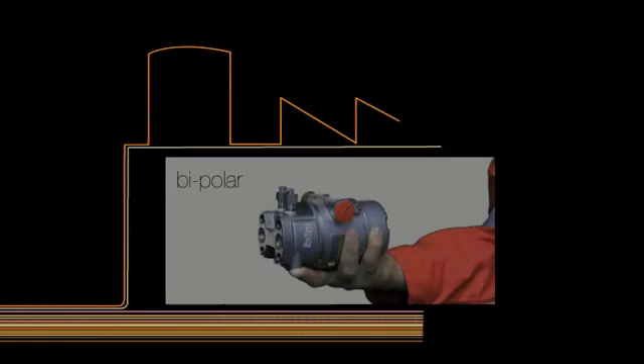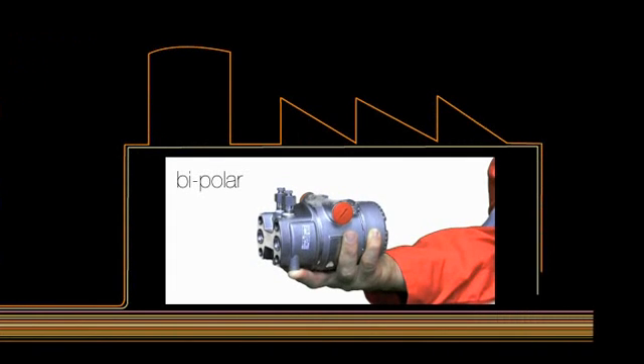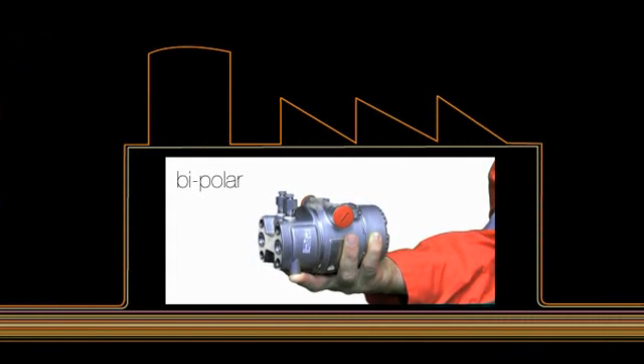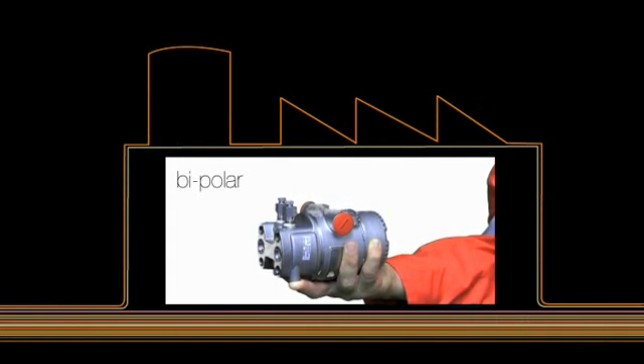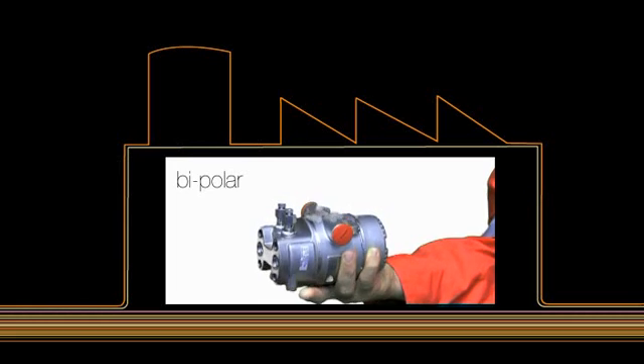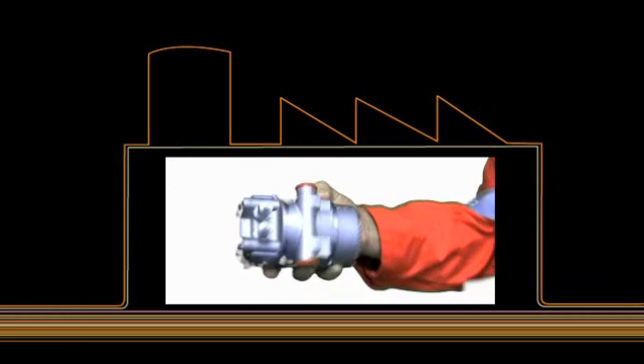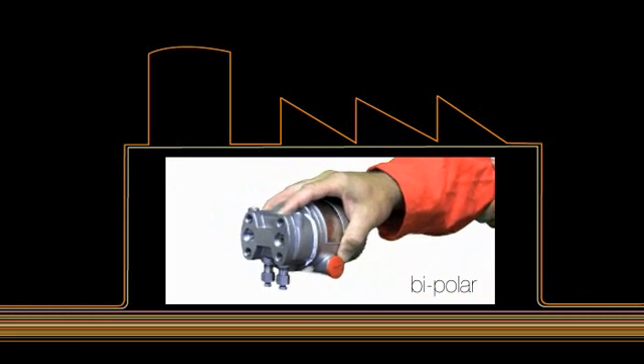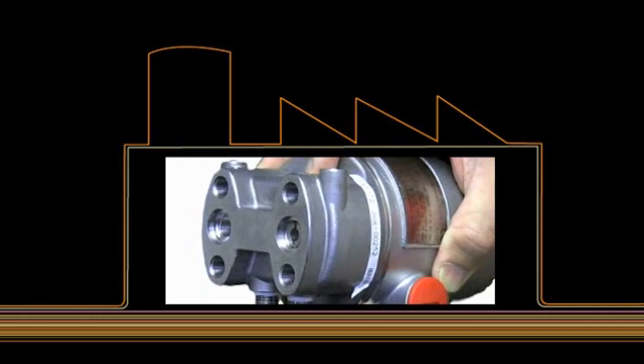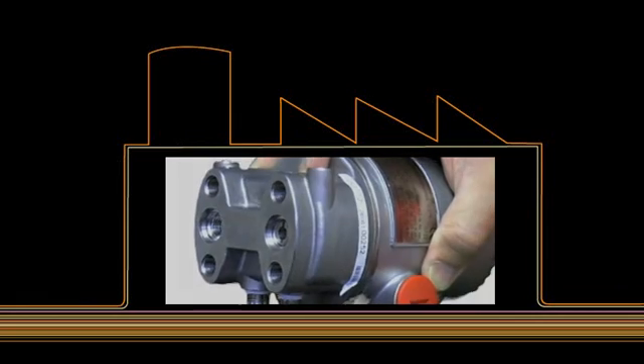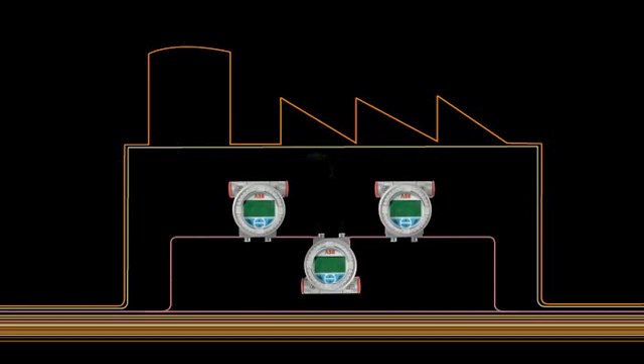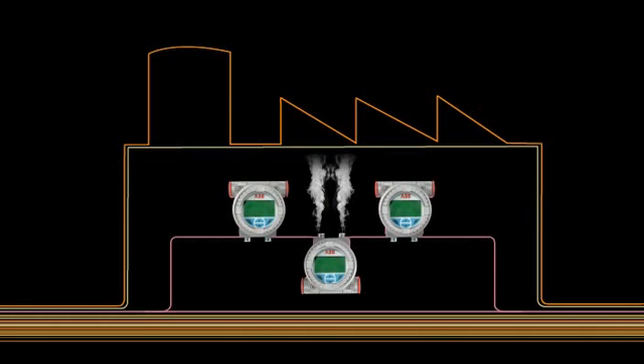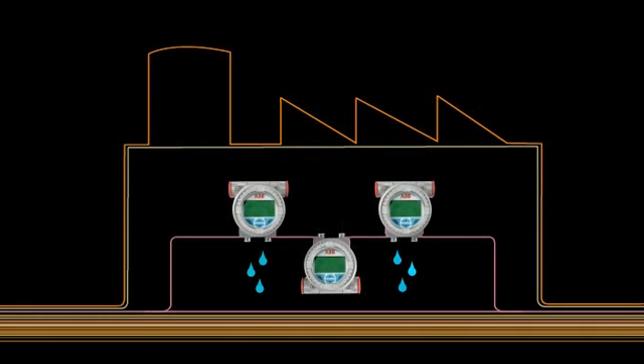The differential pressure version is designed to be bipolar, so it doesn't matter on which port the high or low pressure connection is made. The transmitter can be configured afterwards when commissioned. The only decision you have to make is whether you need the vents facing up to vent gas from liquid pressure applications or facing down to vent liquid for gas pressure applications.